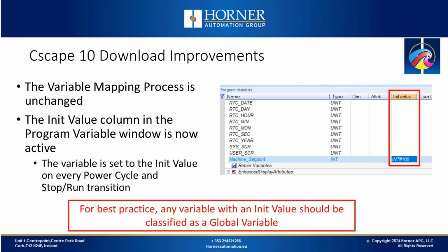With Cscape 9, global variables strictly initialize based on their register location and the retained value of that specific register on power-up. Now with Cscape 10, the initial value column of the program variable window is now active. If you want a global variable to initialize to a specific value, then it can be plugged in by the user in the initial value column of the program variable window. So if a value has been specified in that column, the global variable will always initialize to that value.